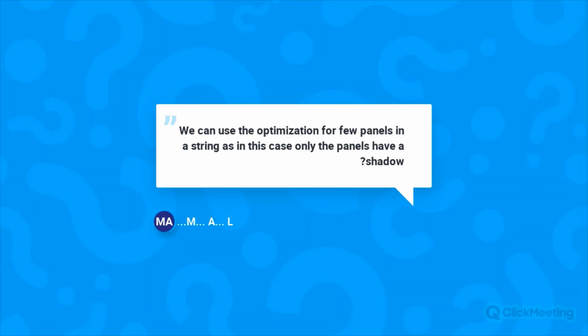Can we use the optimization for a few panels in a string, as in this case only some panels have shadow? Yes, this optimizer supports both partial and full optimization. That's why, in one of the slides, I mentioned the minimum number of optimizers you can use in a string and the maximum number you can use in a string, which means that in between those values, you could use any number. If those are not your total number of PV modules, that is fine. Partial optimization is also well supported.